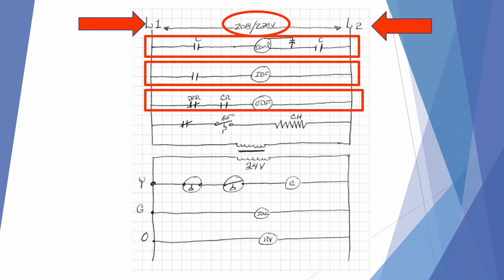On the third line, our outdoor fan motor is controlled by a CR set of contacts and a DFR relay. This is so that the fan will operate whenever the compressor is running, and it will also be brought on and off during the defrost cycle on a heat pump.